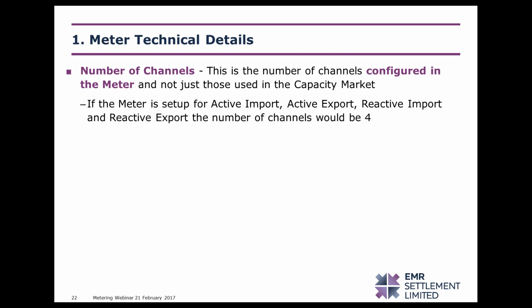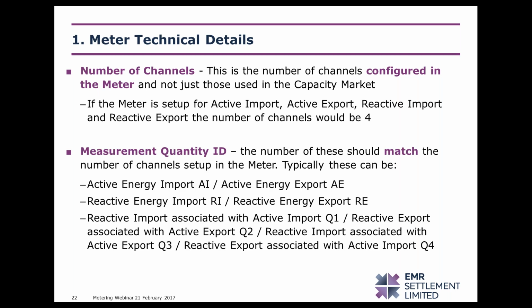So if your meter was set up for active import, active export, reactive import, and reactive export half-hourly data channels, the metering statement should state that there are 4 channels. It is irrelevant that only the active export channel may be actually used for settlement in the capacity market. If in this situation you put down 1 channel, the metering test would be failed because it does not reflect the configuration of the meter.